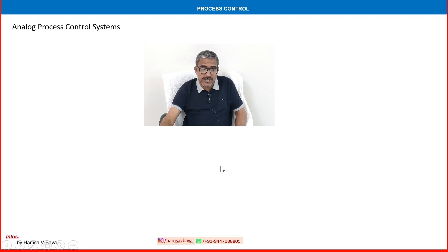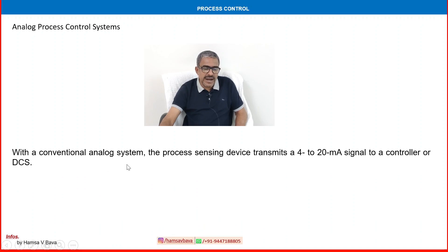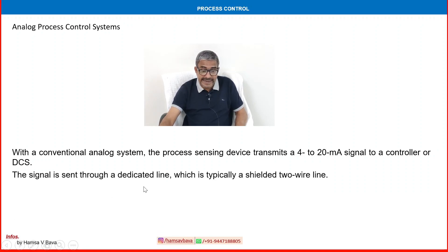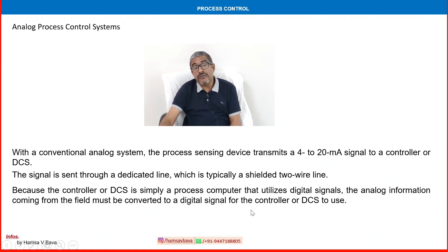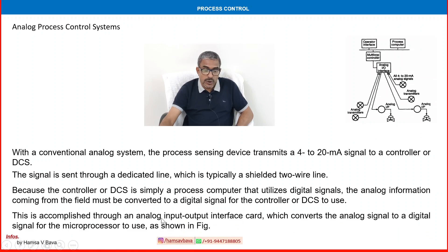With a conventional analog system, the process sensing device transmits a 4 to 20 milliamp signal to a controller or DCS. The signal is sent through a dedicated line, typically a shielded two-wire line. Because the controller or DCS is a digital process computer, the analog information coming from the field must be converted to a digital signal. This is accomplished through an analog input-output interface card, which converts the analog signal to a digital signal for the microprocessor to use.